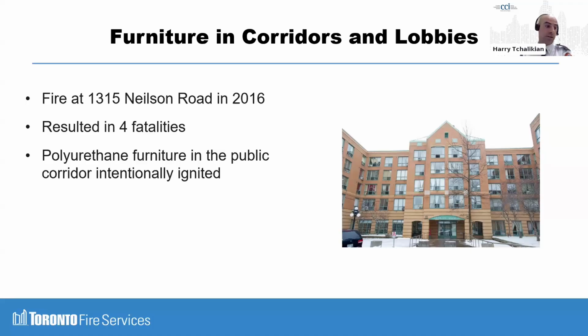So after this fire, we looked at the existing codes, and all we had to work with was 2.4.1.1 sentence 2 that said combustible materials shall not be accumulated in any part of an elevator shaft, ventilation shaft, means of egress, service room, or service space unless the location, room, or space is designed for those materials. That was problematic wording. It was unenforceable for this specific situation because it looked like it was designed for that purpose. And placing furniture is not really an accumulation of combustibles. So that situation was relatively unenforceable, and this fire exposed that.